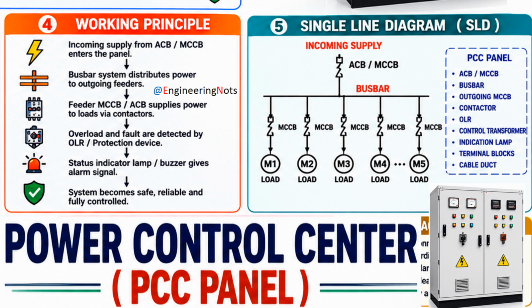In this diagram, power enters from the transformer. It passes through the incoming breaker and reaches the main bus bars. From there, the power is divided into several outgoing feeders. Each feeder supplies a different electrical panel or a different section of the plant. Although the drawing looks simple, it contains all the essential information needed to understand how power is distributed. That is why every electrical engineer should know how to read a single-line diagram.